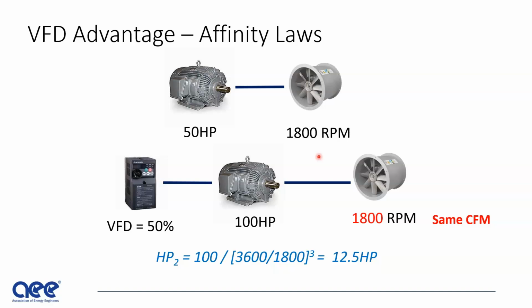You save more money. But your first cost includes the cost of the VFD and the cost of the larger motor. And you've got more points of failure. You've got increased maintenance. So you have to factor all these into the equation before you just go and do this. But technically speaking, if I'm running this motor for the next 20, 30, or 40 years with this arrangement, I'm thinking I'm better off with the VFD on 100 horsepower to run that fan.